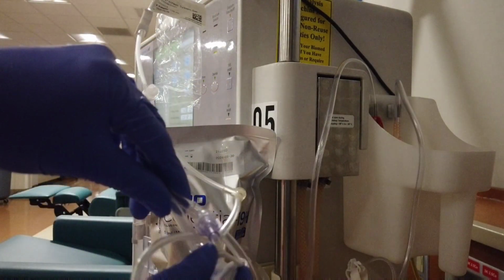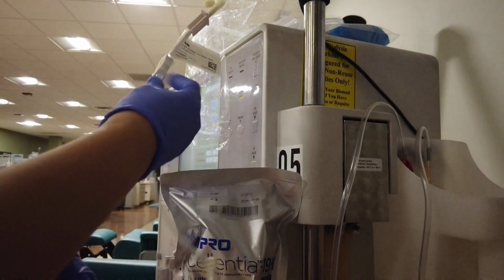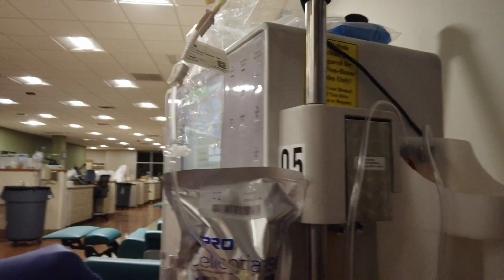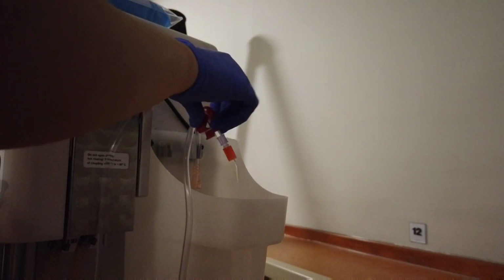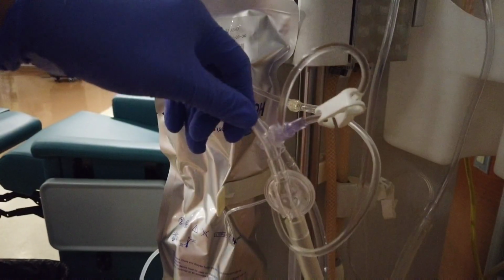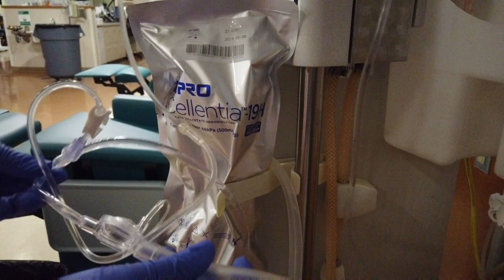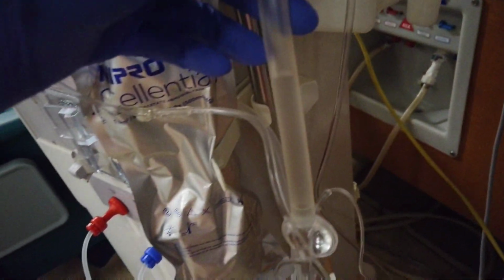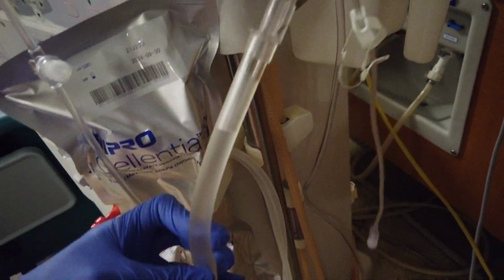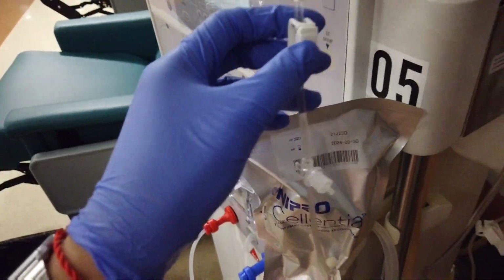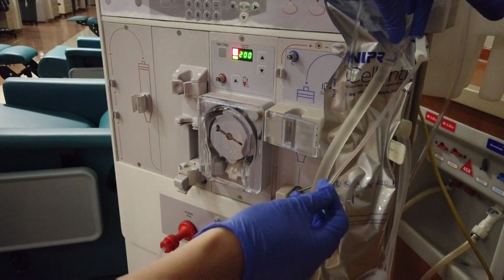Then open the 2 clamps of the infusion line. Once the saline reaches the arterial patient's end, clamp the huge red clamp. Next, prime the arterial dialyzer end line by gravity, releasing the kink and holding the blood pump segment in an upright position with the arterial pressure pod at the bottom. Once saline reaches the arterial dialyzer end, close the top clamp of the infusion line. Don't forget to clamp also the heparin line.